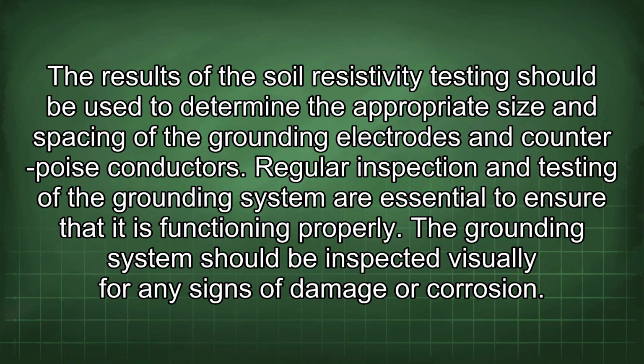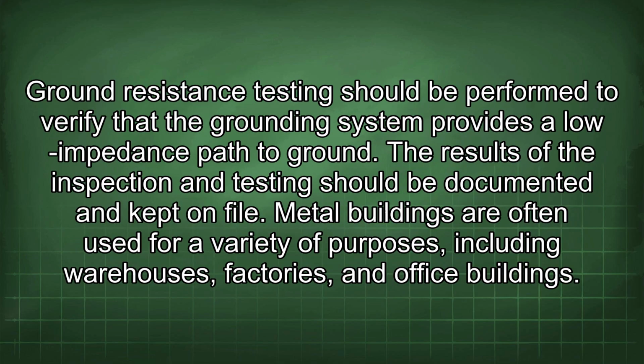electrodes and counterpoise conductors. Regular inspection and testing of the grounding system are essential to ensure that it is functioning properly. The grounding system should be inspected visually for any signs of damage or corrosion. Ground resistance testing should be performed to verify that the grounding system provides a low impedance path to ground. The results of the inspection and testing should be documented and kept on file.